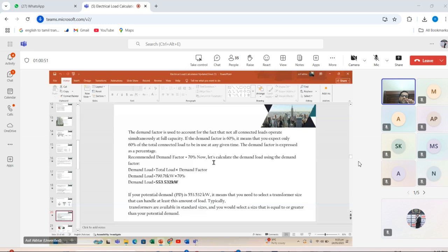Now let's calculate the demand load using the demand factor. The formula is: demand load is equal to total load multiplied by demand factor. We assume the demand factor is 70%. So our calculation is 790.76 multiplied by 70%, so the demand load is 553.53 kilowatts. If your potential demand is 553 kilowatts, you need to select a transformer size that can handle at least this amount of load. Typically transformers are available in standard sizes, and you would select a size equal to or greater than your potential demand.